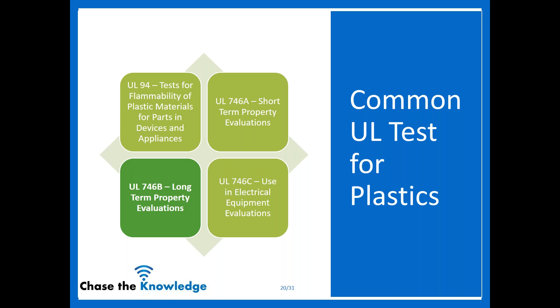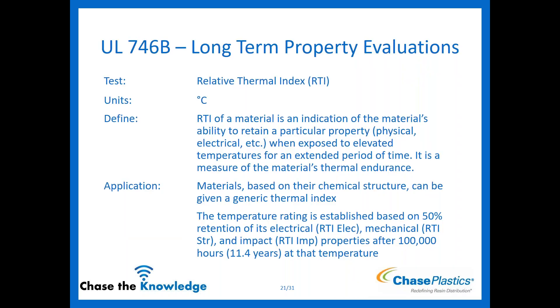Now we're going to talk about UL 746B — your long-term property performance. This is going to be your RTI, Relative Thermal Index, given in degrees Celsius. It's basically the material's ability to retain a certain amount of its properties — specifically 50% — when exposed to elevated temperatures for an extended period of time. The whole gist is: at what temperature, after 100,000 hours (which equates to about 11.4 years), is the material going to maintain at least 50% of its original value for electrical, mechanical, and impact properties?